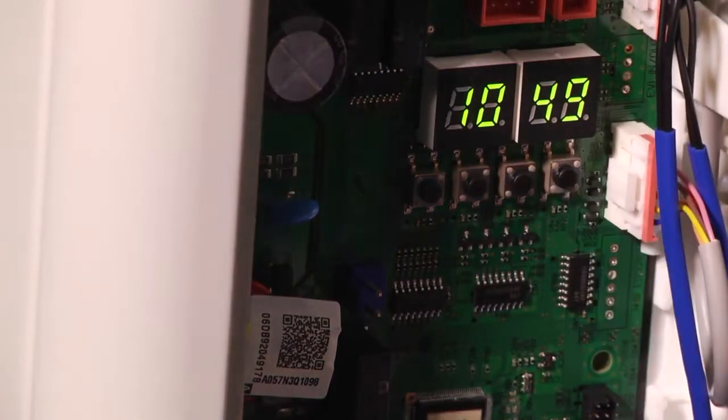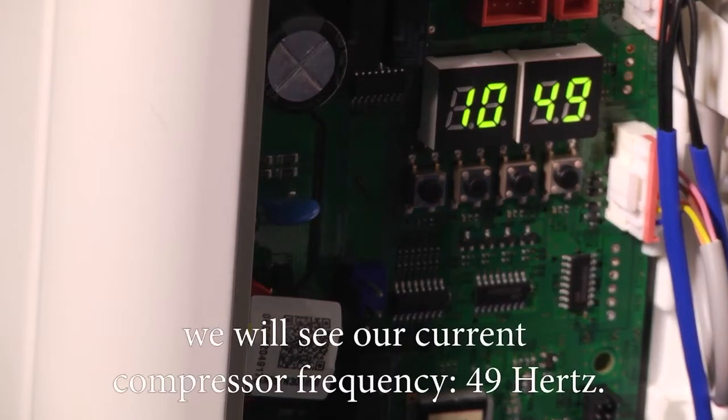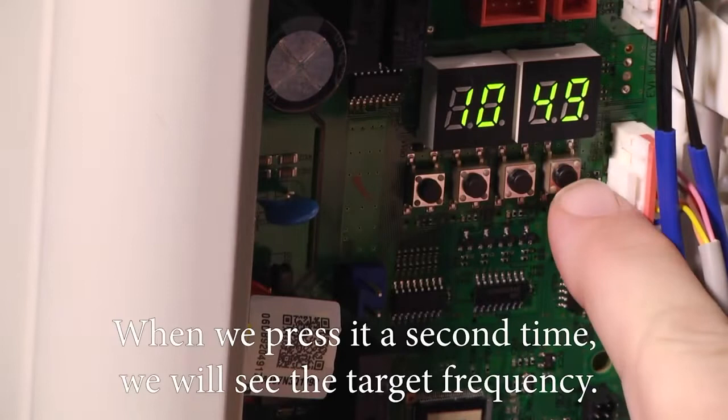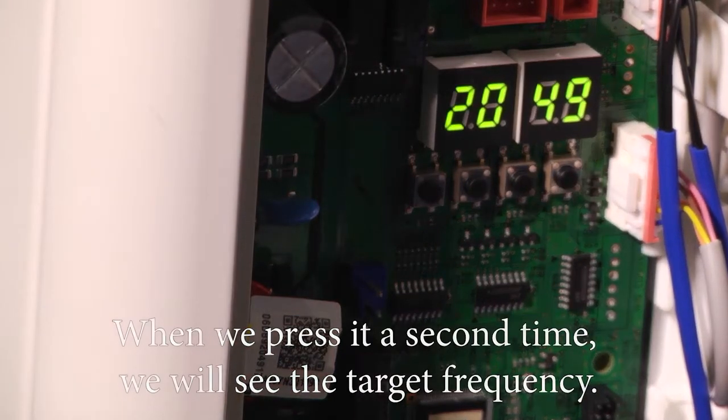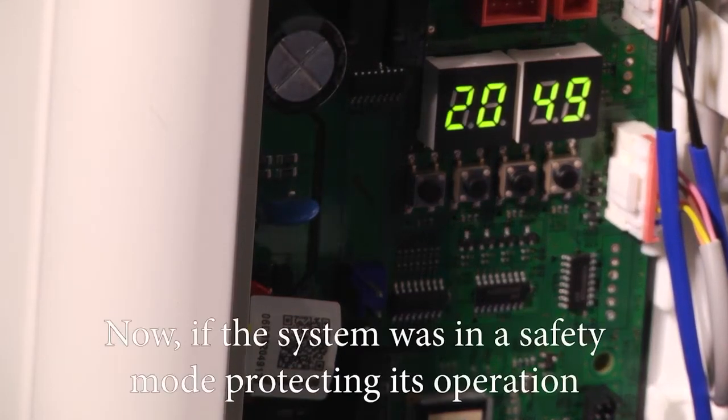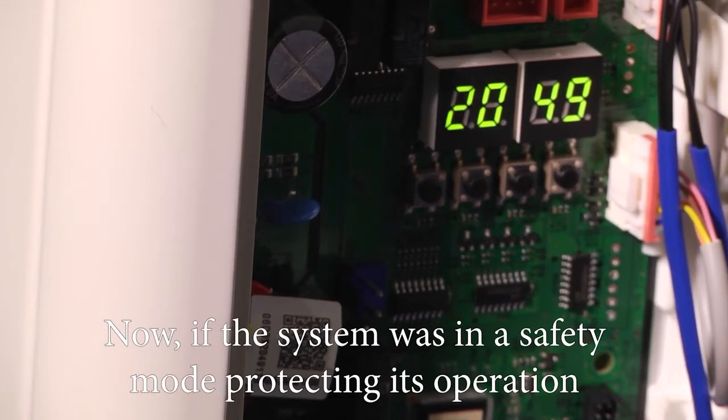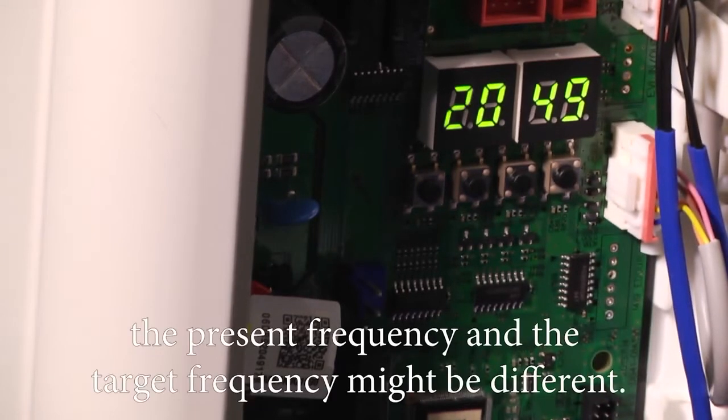When we press the K4 button once, we'll see our current compressor frequency, 49 Hertz. When we press it a second time, we'll see the target frequency. Now, if the system was in a safety mode protecting its operation, the present frequency and the target frequency might be different.